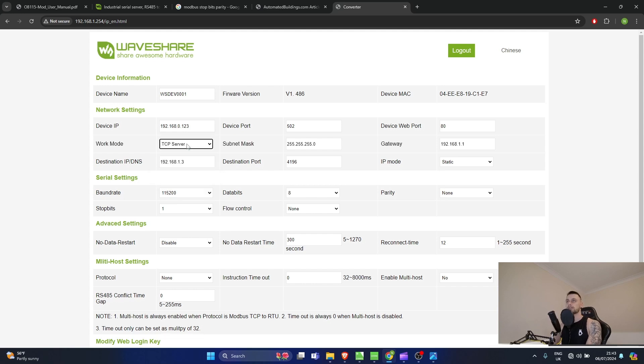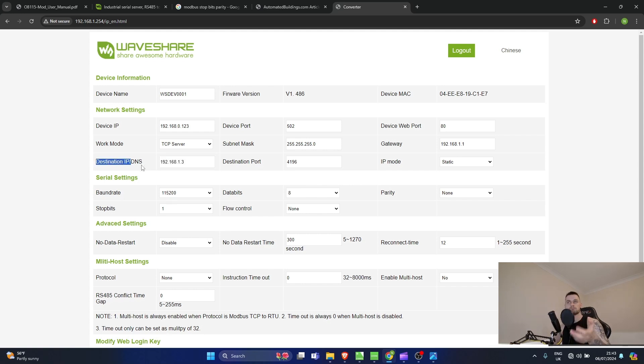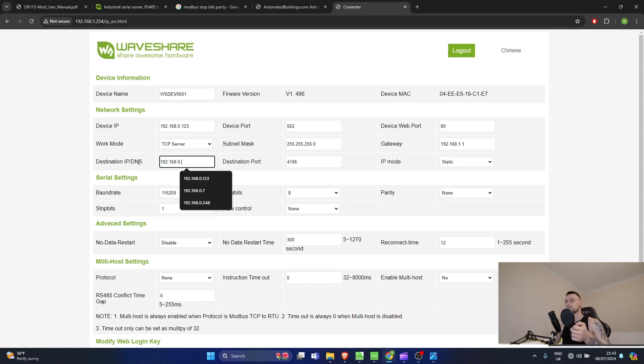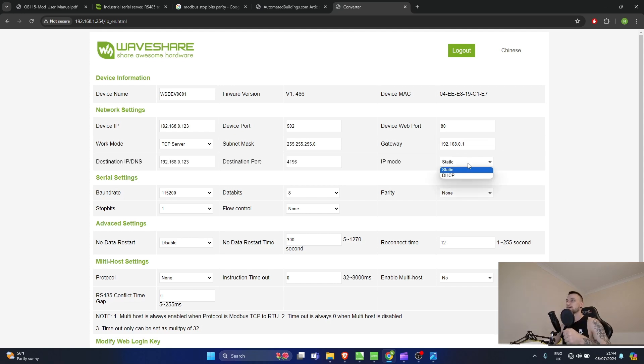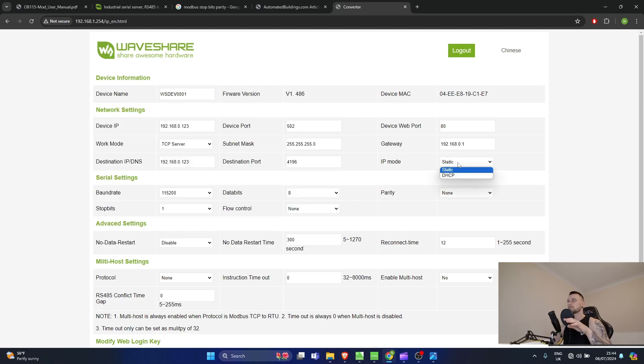It's set as a TCP server and I'll leave it that way. The destination IP is a bit confusing - it seems like a translation issue - but I'll set it to 192.168.0.123 and leave the destination port as default. The gateway will be 192.168.0.1, matching my actual router. For IP mode, I'll leave it on static, though in some situations I'd recommend DHCP with a DHCP reservation from the router.